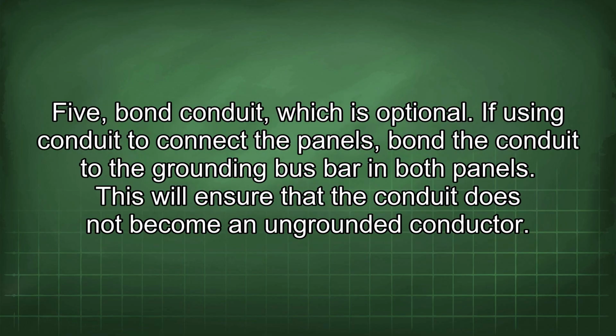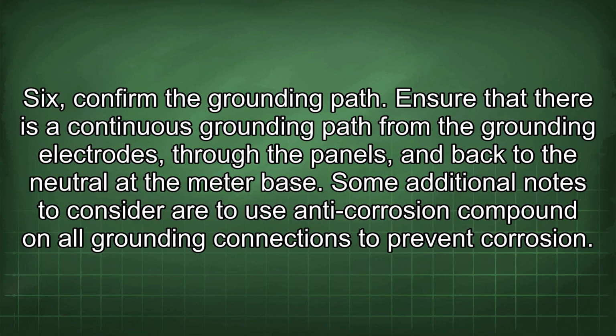5. Bond conduit, which is optional. If using conduit to connect the panels, bond the conduit to the grounding bus bar in both panels. This will ensure that the conduit does not become an ungrounded conductor. 6. Confirm the grounding path. Ensure that there is a continuous grounding path from the grounding electrodes through the panels and back to the neutral at the meter base.